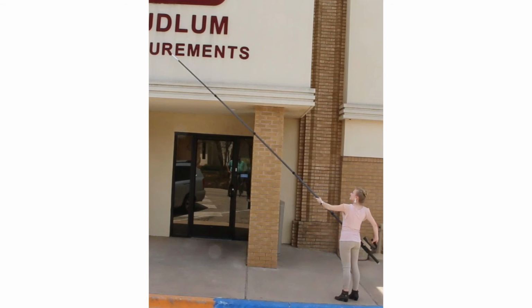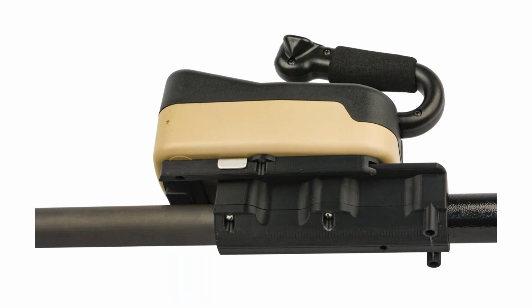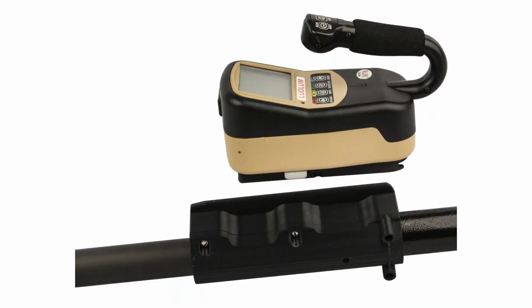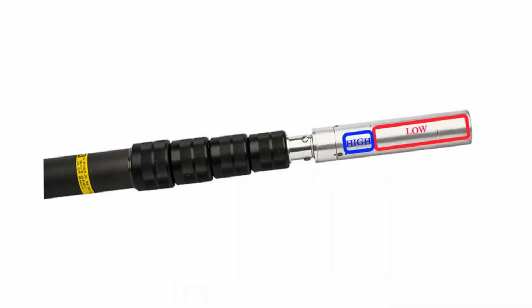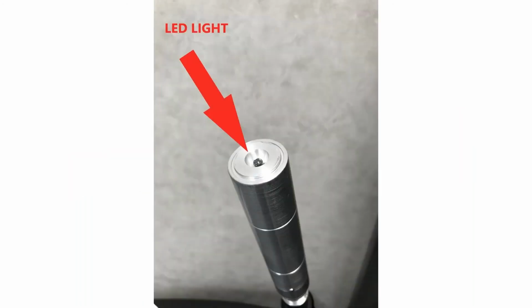It has a retracted length of 1.3 meters or 4.1 feet, and an extended length of 4.7 meters or 15.3 feet. The 3078 has electronics that can be easily detached for the ease of battery replacement. The 3078 and 3078i feature an external detector housing on a telescoping mast that contains 2 GM detectors, one for low range, one for high range. These can be either controlled individually or can auto range depending on the strength of the radiation field. The external detector housing also includes an LED lamp to illuminate inspection areas in low light situations.